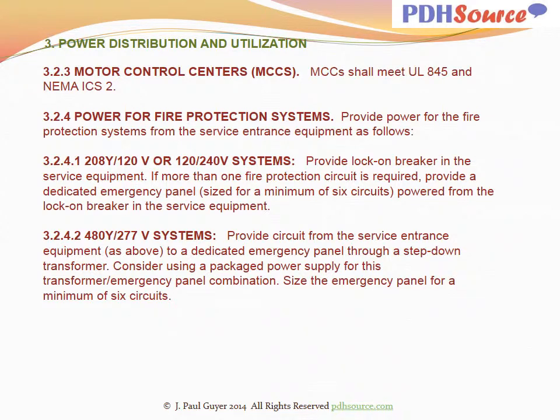Motor control centers shall comply with Underwriters Laboratories 845 and NEMA ICS2. With regard to power for fire protection systems, provide power from the service entrance equipment as follows: 208Y/120 volt or 120/240 volt systems. Provide a lock-on breaker in the service equipment.